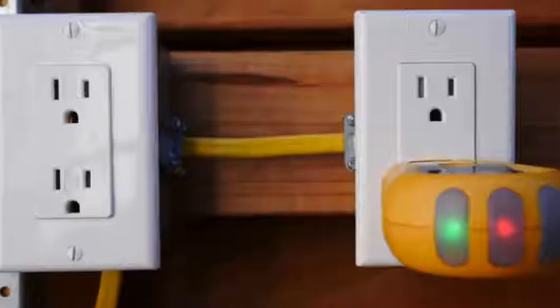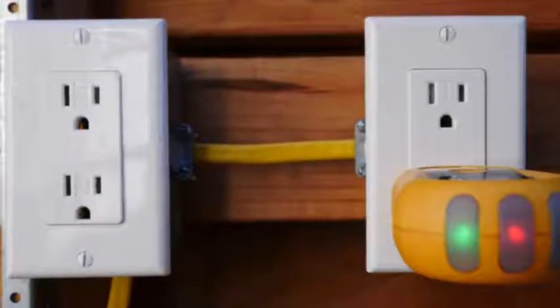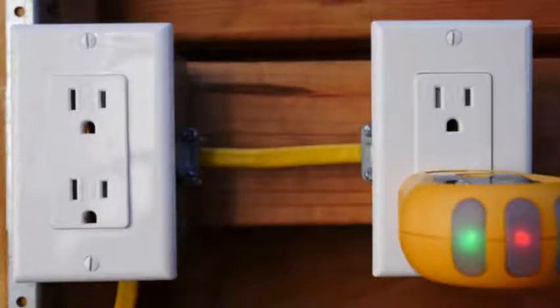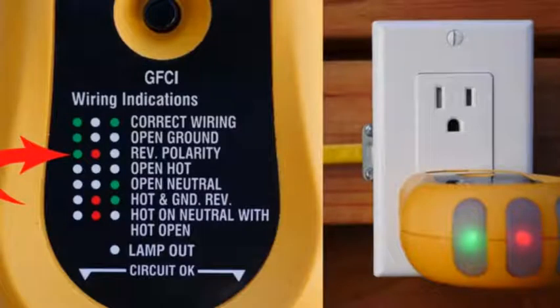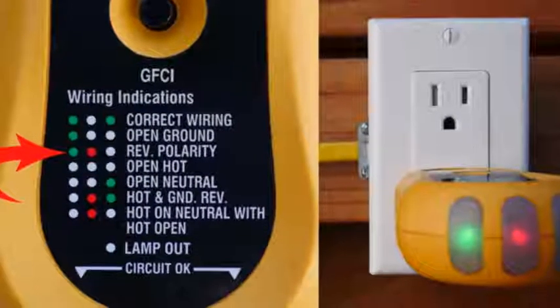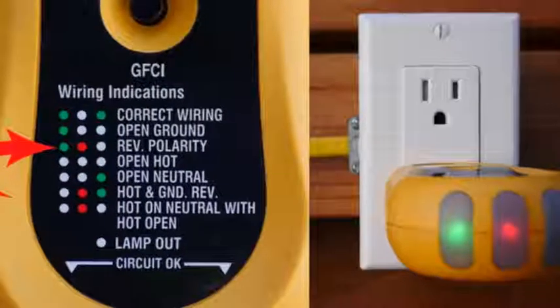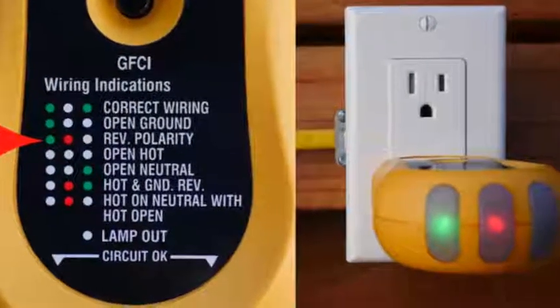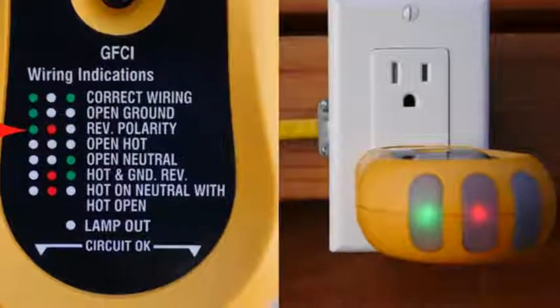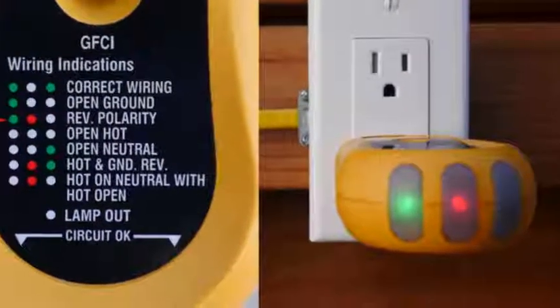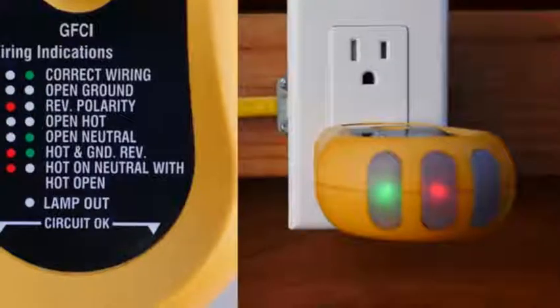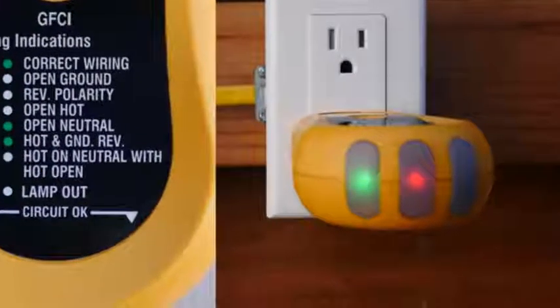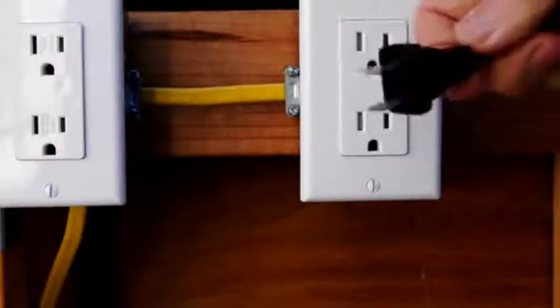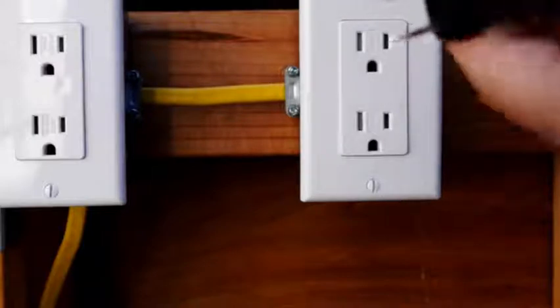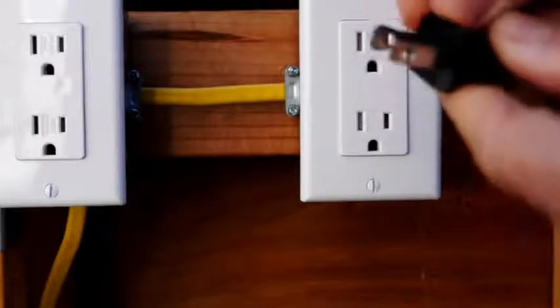Hi, this is Bill for SparkyChannel.com, and today I'm going to show you how to fix a receptacle that has reversed polarity. To find out if your receptacle has reversed polarity, what you would need to do is plug in an outlet tester like this one and look at the index on it. On this particular outlet tester, the index shows us that if there's a green light on the left and a red light in the middle and an open light on the right, then we have reversed polarity. What this means is that the hot and the neutral are reversed on the receptacle.